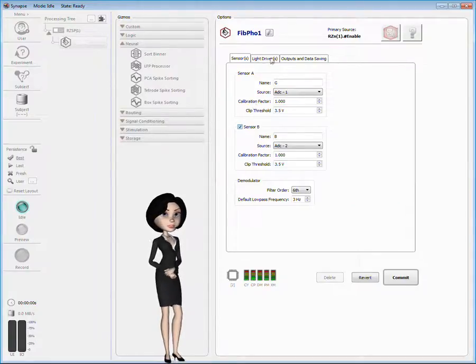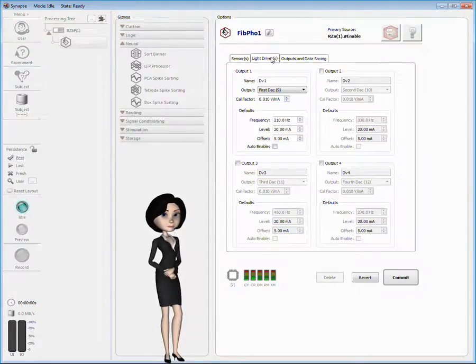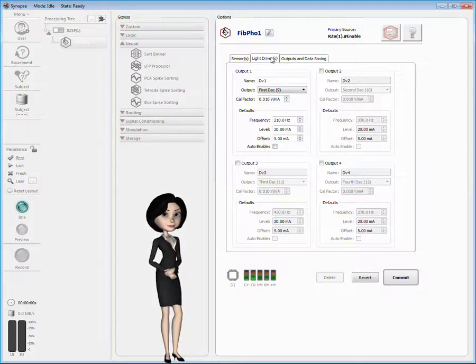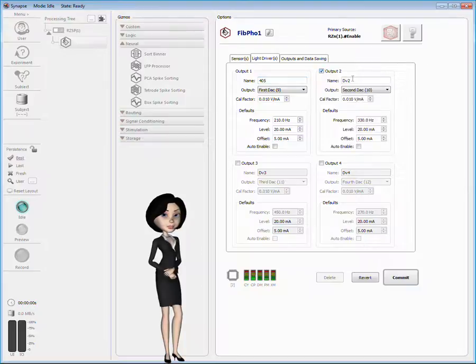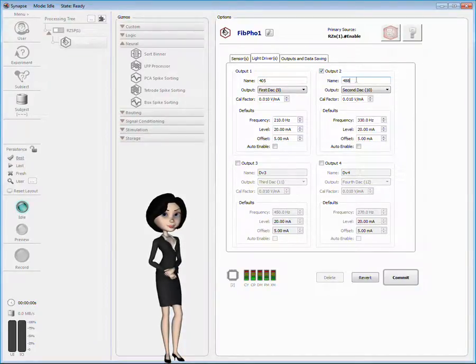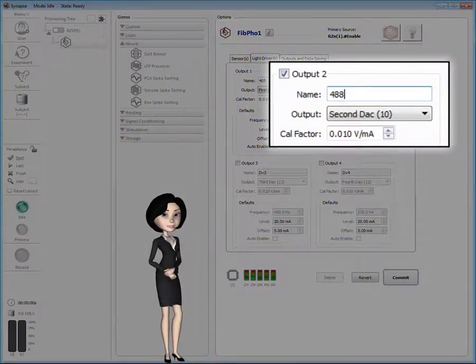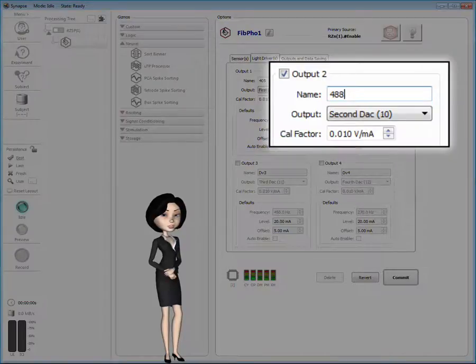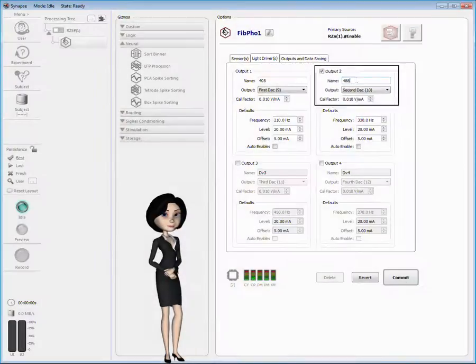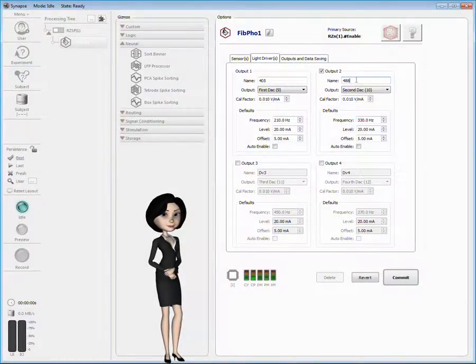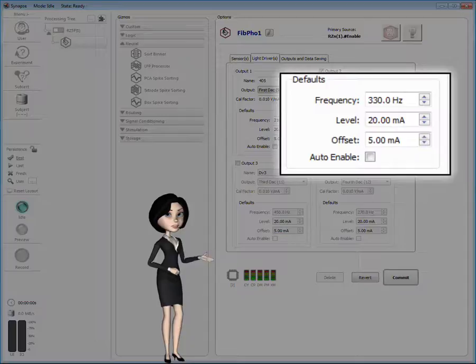On the Light Drivers tab, I can configure up to four drivers. Each driver has a three-character name. Typically, you'll set this to the light color or wavelength. You can set a calibration factor for each driver to convert the voltage values used by the TDT processor to milliamps. The default values shown here are the initial values for the parameters used for the light driver.